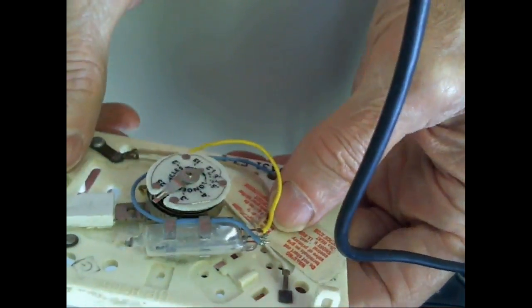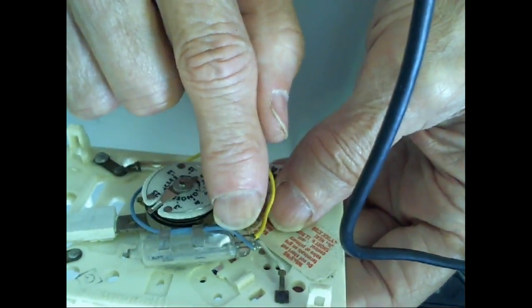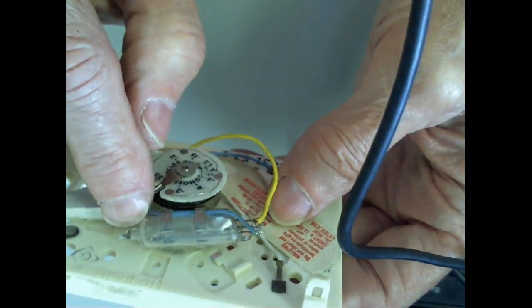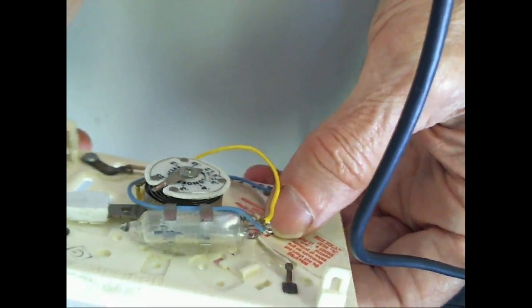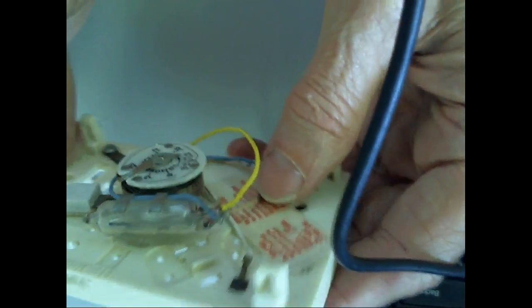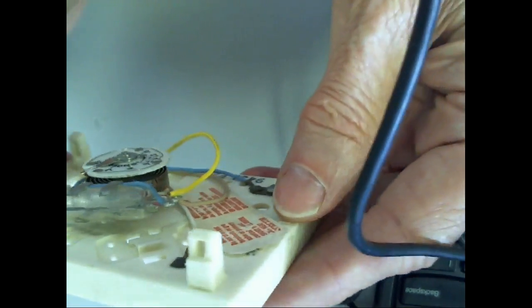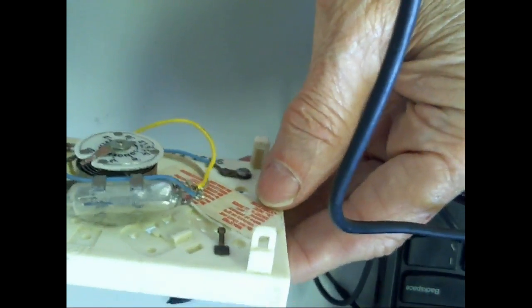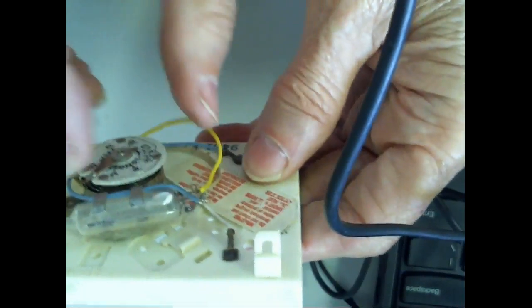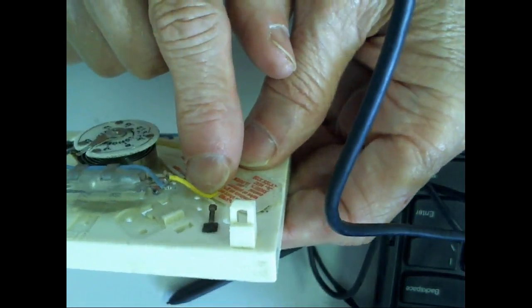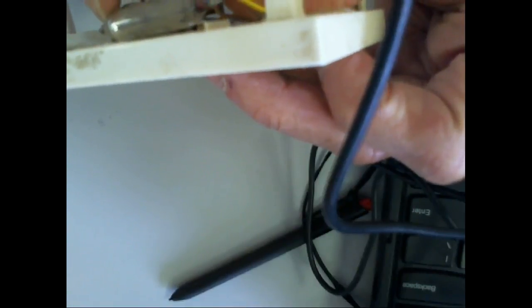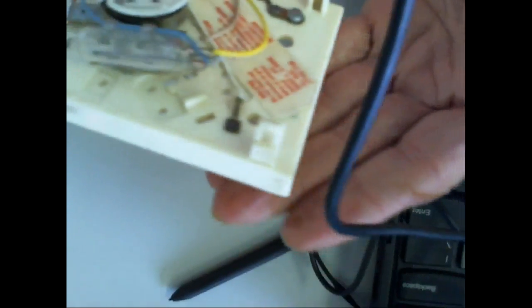And what would happen is at the top, we have what type of switch? Mercury switch. And you'll watch, it's got two terminals right here, and then it's got one that comes over to the other side, and it's got two terminals on that side right there. So one of them would work for heat, and the other one will work for your air conditioner. Pretty neat, right? So what happens is when this thing heats up, it would come out of the loop, and it would cause the mercury switch to tilt. So it breaks this set of contacts on this side, but it did what? It made them on that side. So it depends on whether you had it on your air conditioner or on your what? Heater.